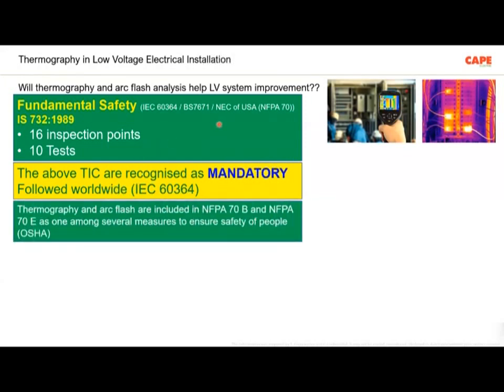Now, if you are doing these testing, inspection, and certification (TIC) points, these are actually mandatory. These are recognized as mandatory safety measures, which are followed worldwide, because IEC 60364 is followed across the globe as the basic electrical safety requirement. Now, in the American standards NFPA 70B and 70E, for OSHA or to comply with the other enhanced safety measures, additional safety measures, or let us say extras, thermography and arc flash studies are considered as one among several measures. Please understand, one among several measures.